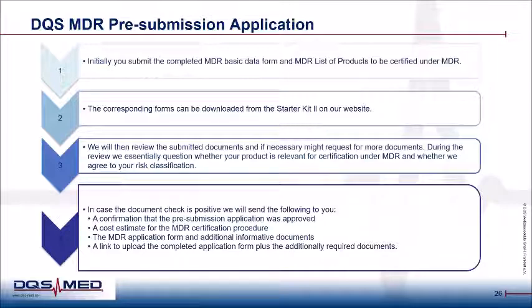So in the same moment when you file the application to a notified body, that's not specific to DQS MED, that's specific to the MDR procedure, you have to provide the technical file, the actual technical file for the product that you applied for. In the same way, we also provide an upload link to you, where you can store the files for DQS MED's evaluation procedure.